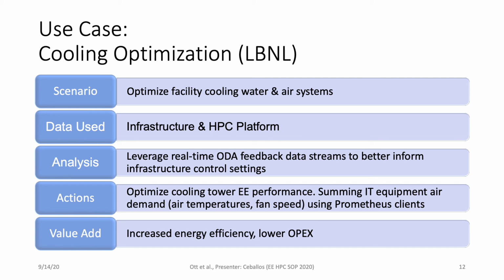The second example is better estimation of cooling supply air demand. Another optimization project underway at NERSC is to leverage the Omni system, which uses Prometheus clients installed on facility air-cooled IT equipment. The client reports the intake air temperature and fan speeds of the IT equipment, giving NERSC the ability to sum cooling air demand and therefore better inform cooling air handler supply settings.